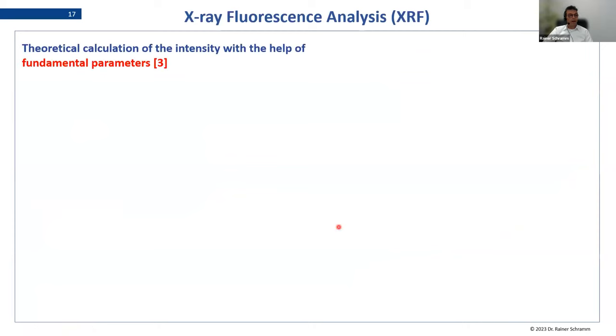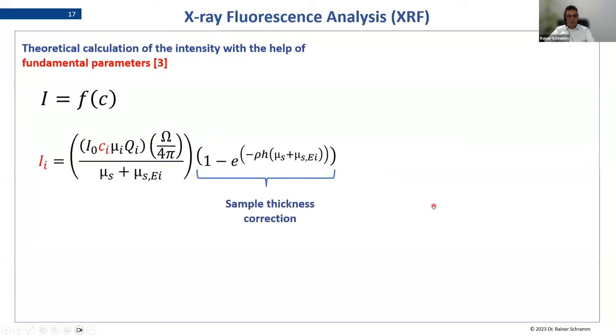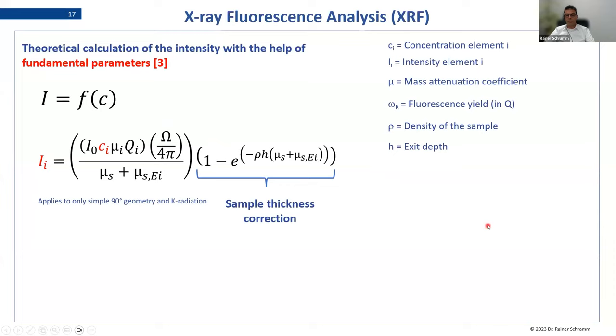Last but not least, we come to the real use of fundamental parameters — calculating the whole approach by describing everything between concentration and intensity using the theoretical approach via the Sherman equation. In theory, no standard material is used. In the real world I would always use some standard materials at least to get the sensitivity of the spectrometer and to verify the model, but from the theory side no standard material is used if all conditions of the model are fulfilled. I described this in the last webinar; here I just want to present it to complete this overview.